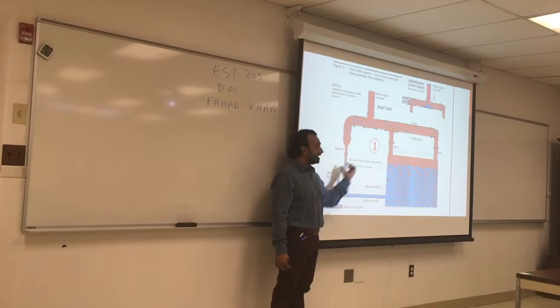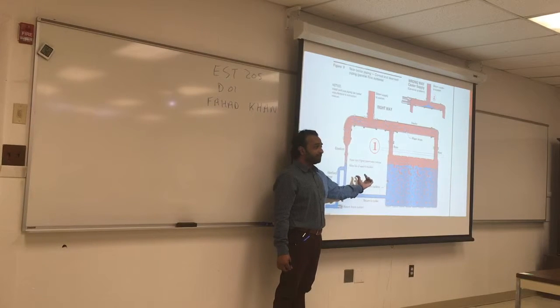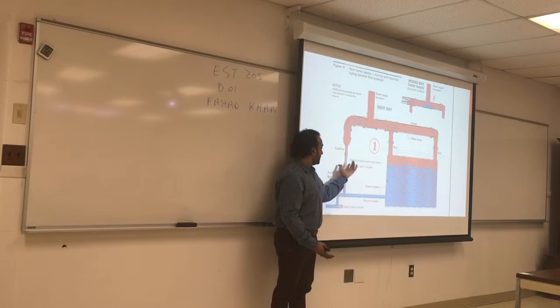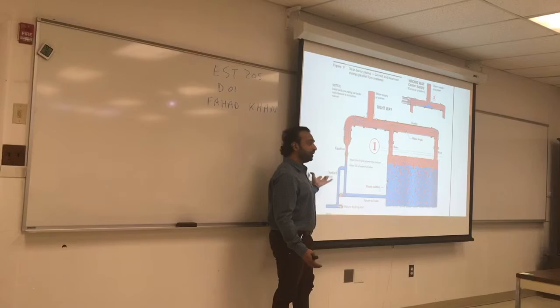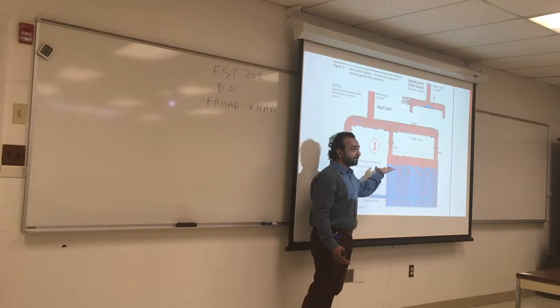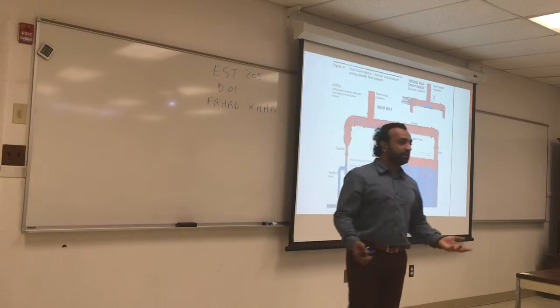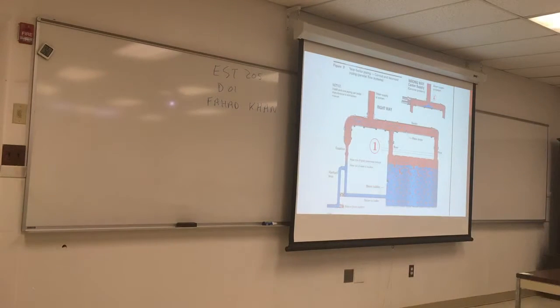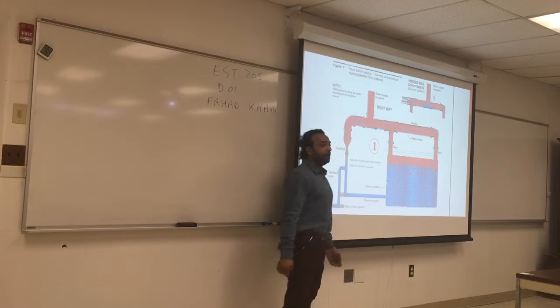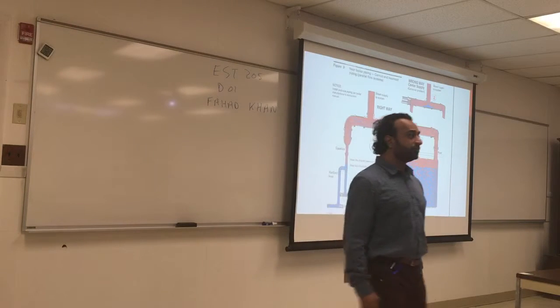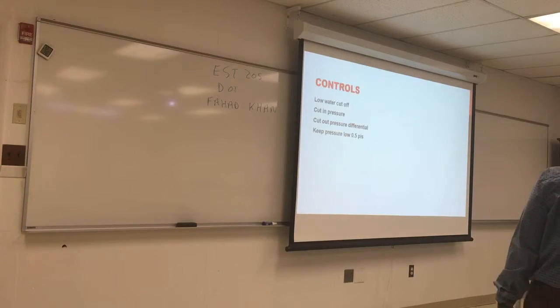Back pressure from the chamber. You have a buildup of steam, something got clogged, and water gets pushed down. It will push the water back through the Hartford loop, but eventually it will slowly come back again. Similar to what you have in some toilets where you have a high water level. If it pushes too much, you will see it slowly coming back again because of the loop, because the water is maintained at that level. The Hartford loop is done for safety and it's mandatory for all steam boilers.